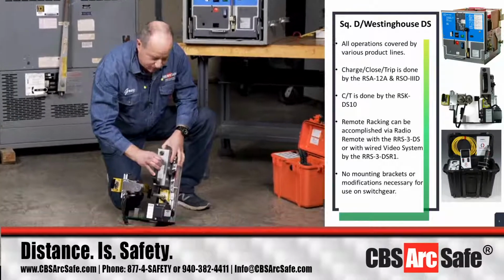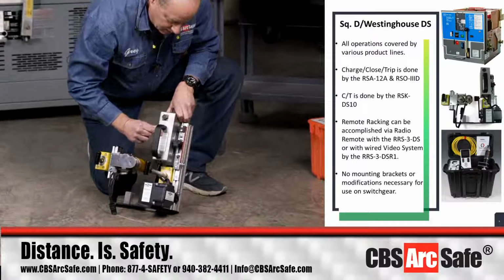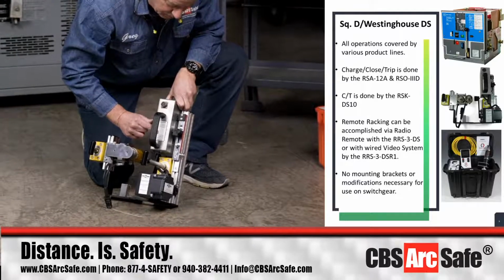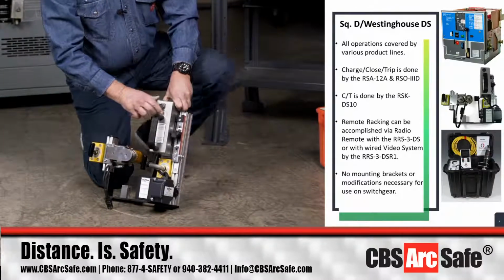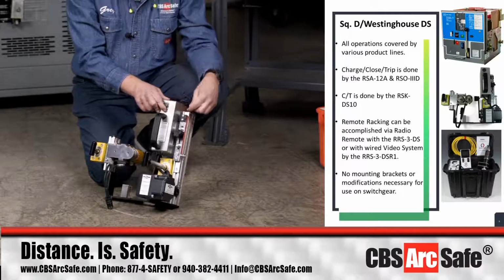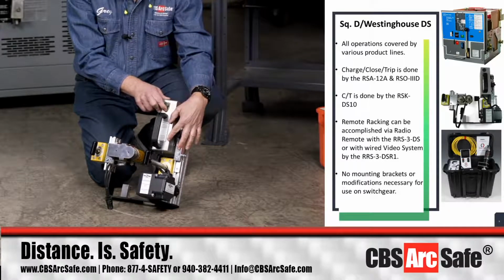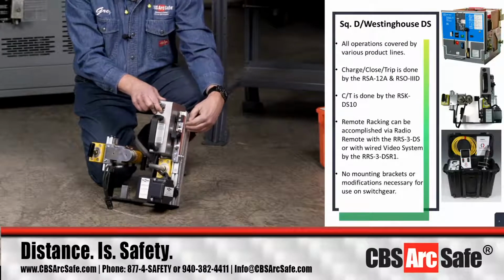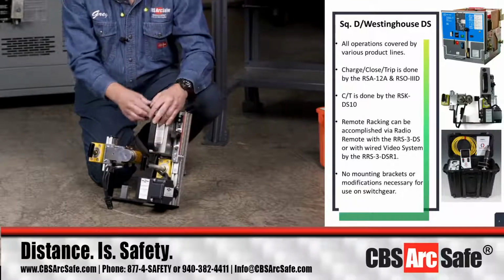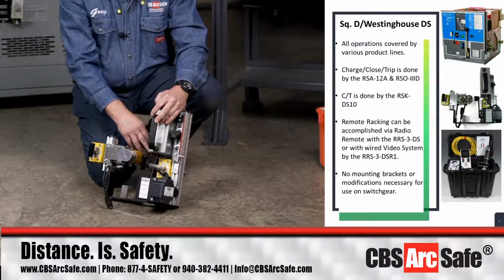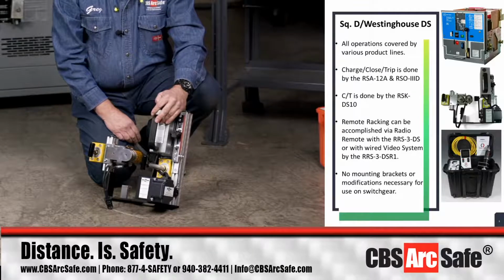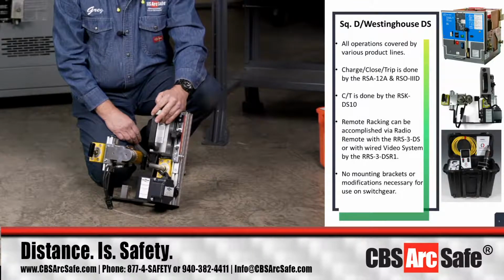I'm going to turn it just a little bit, and it'll ask whether you have an electric breaker or a manual breaker. You're looking in here to make sure you've got it set right, because there are micro switches inside which actuate and change the distance of the stroke travel for the charging arm based on whether you have a manually operated or electrically operated breaker. So make sure you know the difference between the two styles.